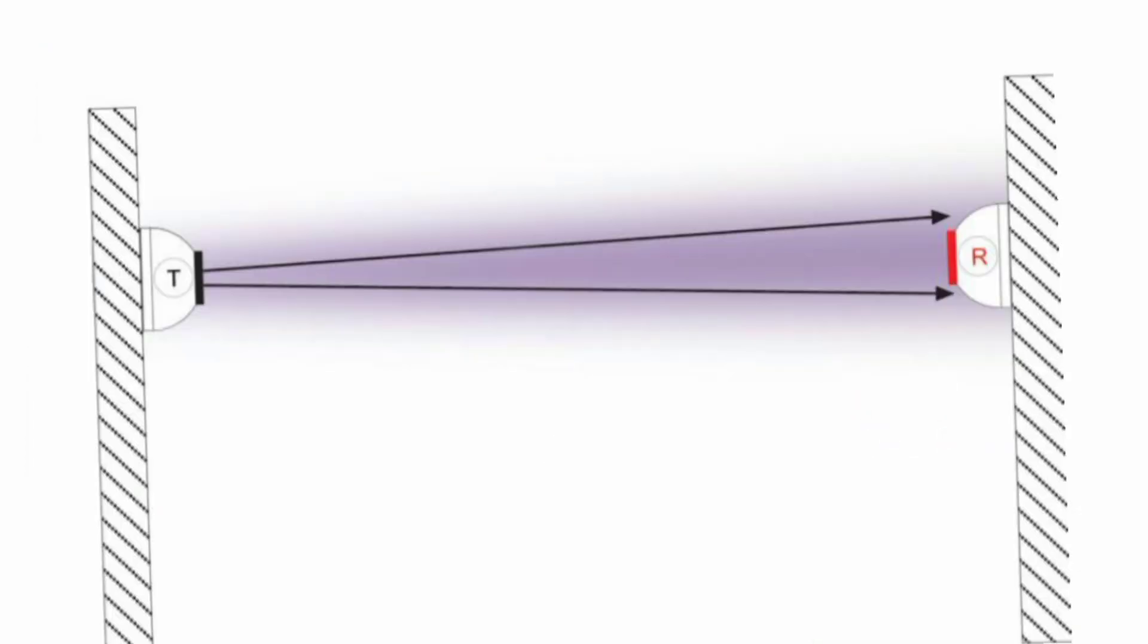In the light-obscuring smoke detector, smoke interferes with a light beam between a light source and photocell. The photocell measures the amount of light it receives. The variation in photocell output is being used to initiate an alarm.